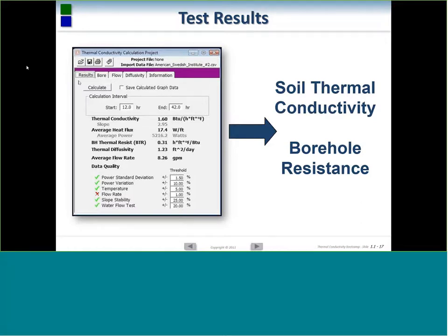And as I said, the thermal diffusivity is more of an approximation based on tabled data. You can calculate thermal diffusivity based on specific heats, densities, and the like. But again, that information sometimes is hard to quantify in a borehole. It really only applies to bedrock formations. Drift, sands, tills, and clays are much harder to classify than bedrock when it comes to calculated diffusivity.